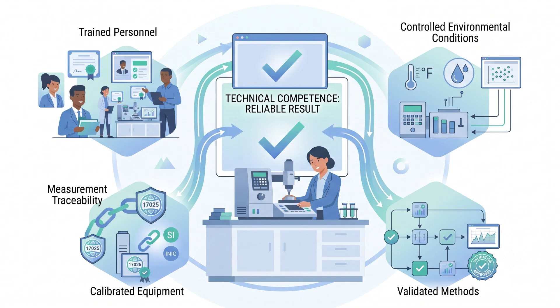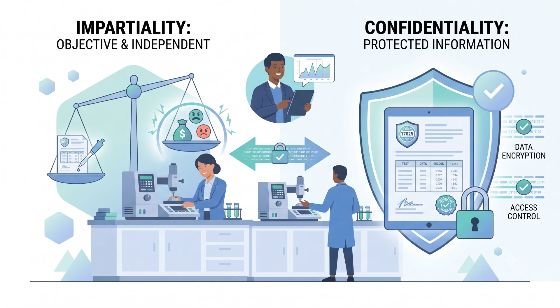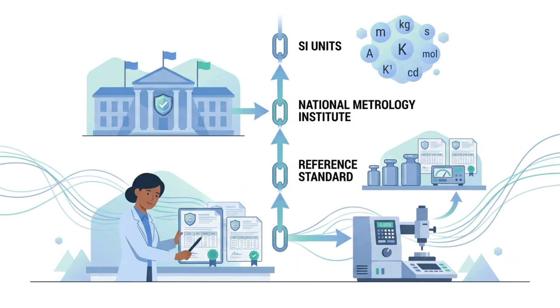Impartiality means that laboratory activities must be carried out objectively and without conflicts of interest or undue influence. Confidentiality ensures that customer information and laboratory results are properly protected. These principles are essential for maintaining trust between the laboratory and its customers. Measurement traceability ensures that measurement results can be linked through an unbroken chain of calibrations to a recognized reference, normally the SI units. For calibration laboratories, this is achieved through appropriate reference standards, valid calibrations, and documented evidence of traceability. Traceability is essential for comparing measurements made at different times and locations.